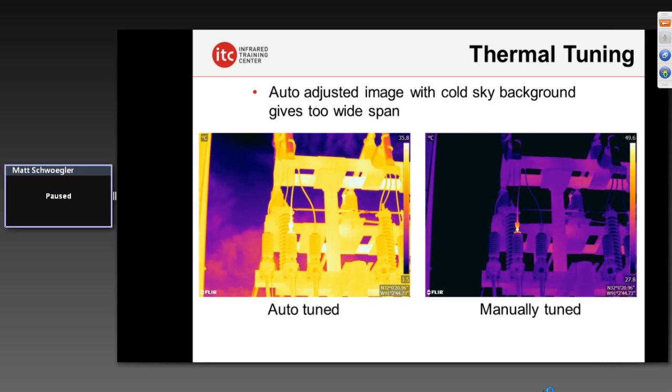Thermally tuning the image — adjusting what's called the span and level — is very important as well. If the scale on your thermal imager's screen is too wide, you're going to potentially miss critical hotspots in the course of your inspection. In this case it's an outdoor substation. On the left, the image has been auto-adjusted by the thermographer with the camera, which automatically sets the span. The width of that span directly affects how much contrast we're going to have on the image.